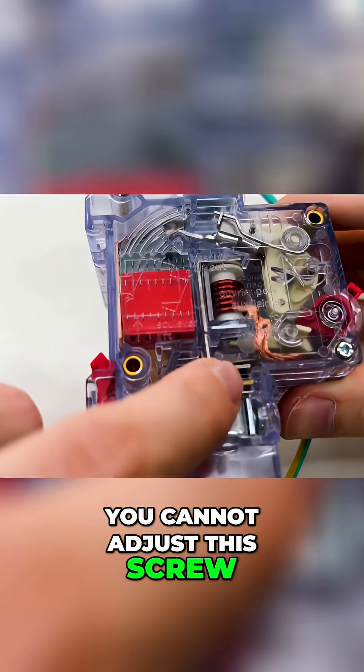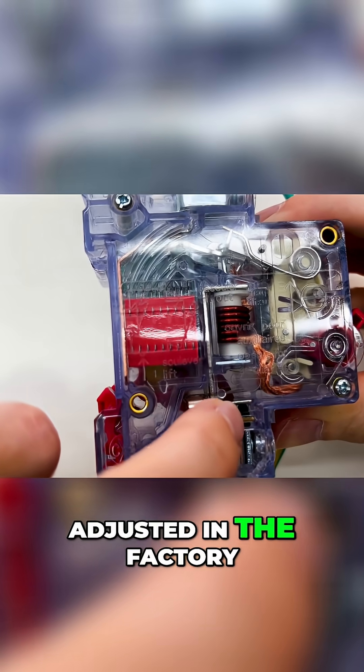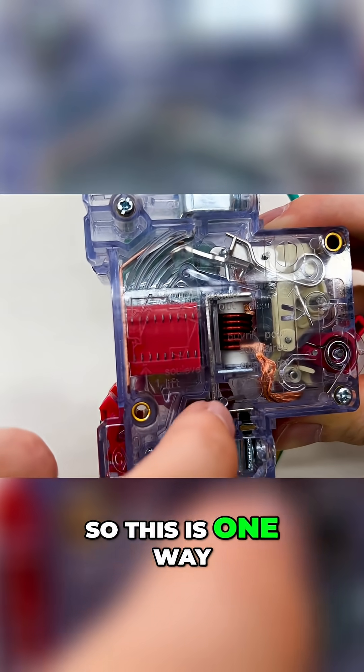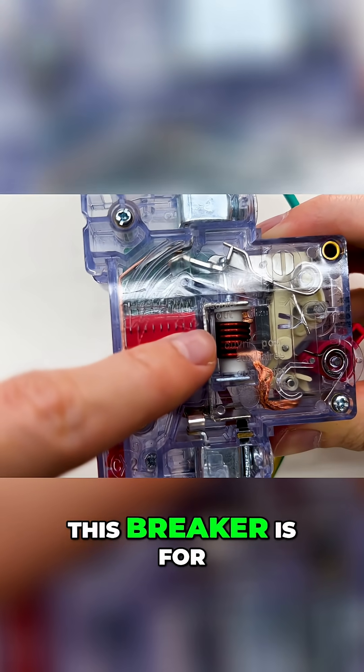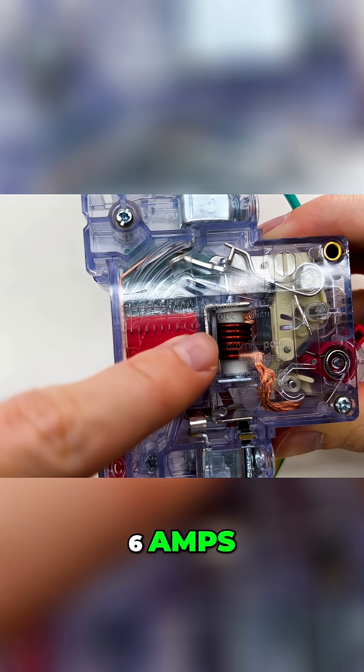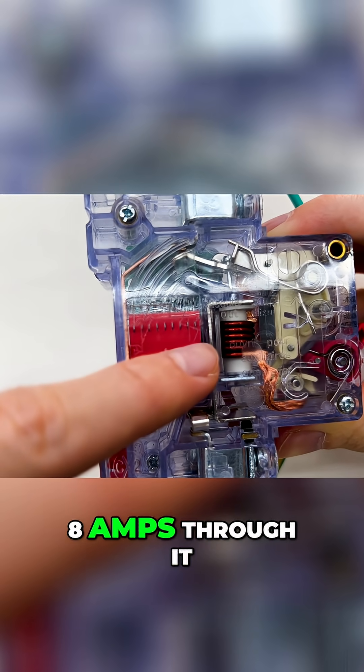You cannot adjust the screw, it is only adjusted in the factory. So this is one way. This is used if, for example, this breaker is for 6A and you would put 8A through it. It would heat up and disable the breaker.